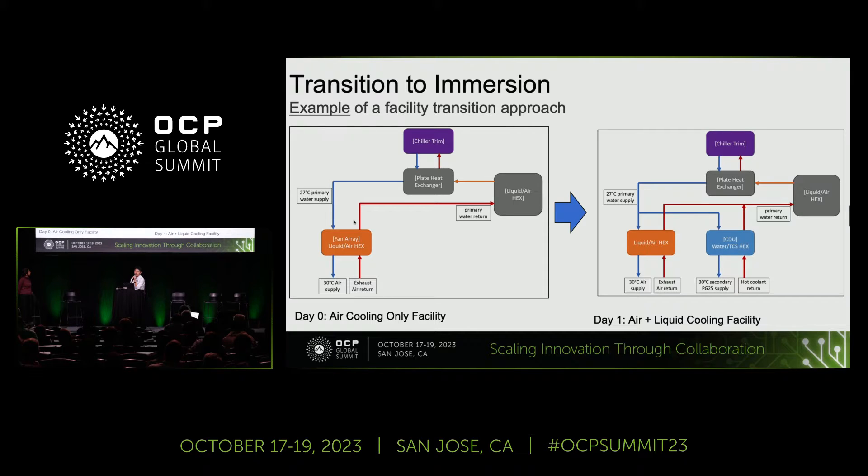Of course, implementation of immersion cooling doesn't happen overnight — the transition needs to happen. As of today, most of our facilities have traditional air cooling enabled. We're showing a simple diagram here going through the dry cooler, chiller trim, and then to the liquid-to-air exchanger, for example the fan arrays which provide air supply to the hardware. It's a clear goal for us to enable liquid cooling for future AI hardware across our fleet, bringing in an extra loop — the water technical coolant solution loop — and bringing PG25-based coolant to cold plates. That's a day-one air plus liquid cooling facility, or a hybrid facility.